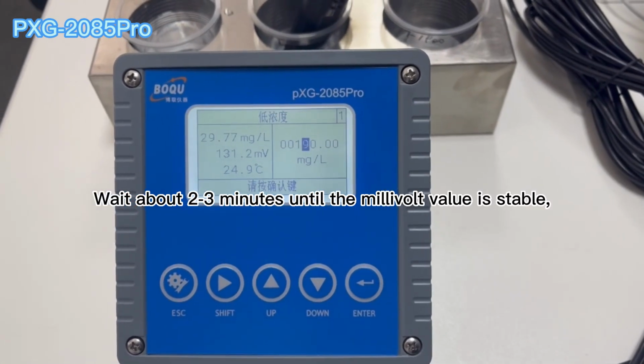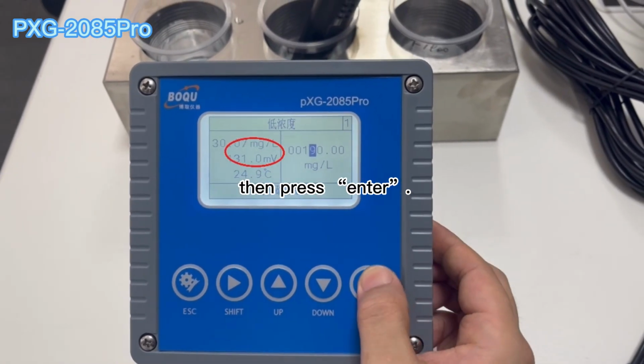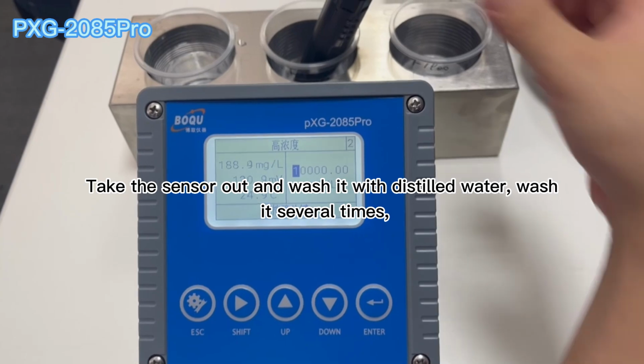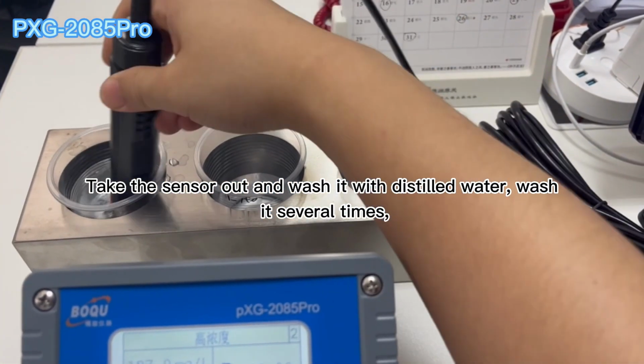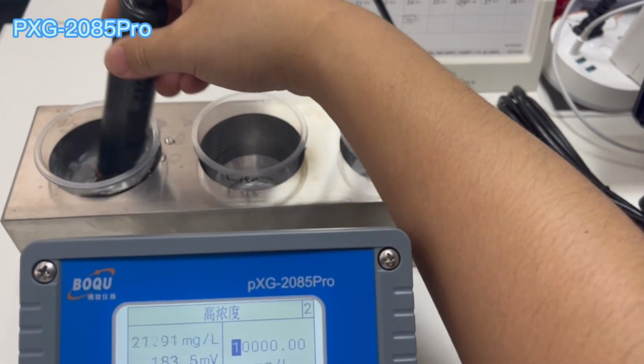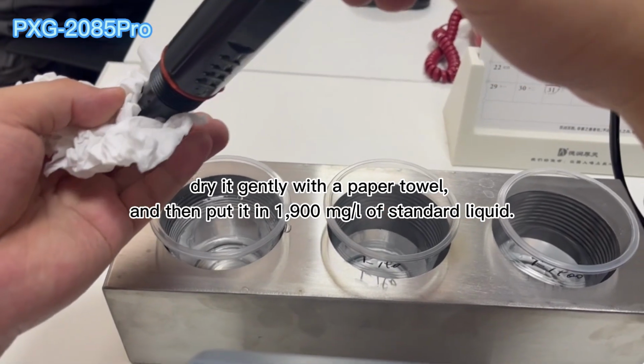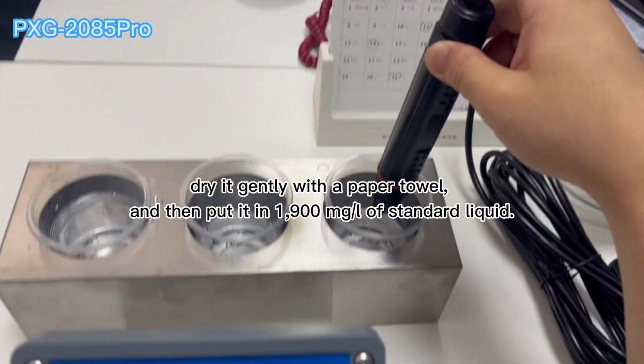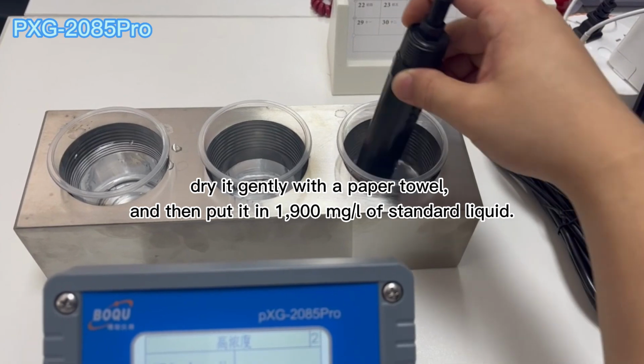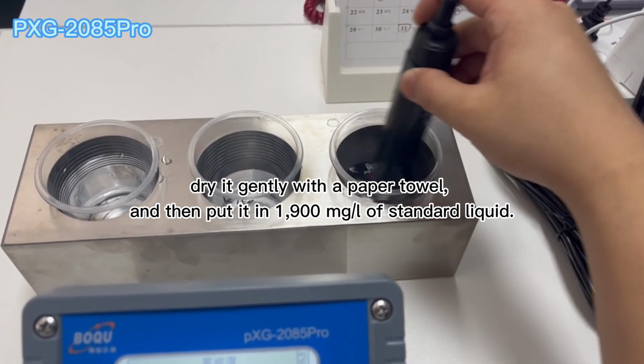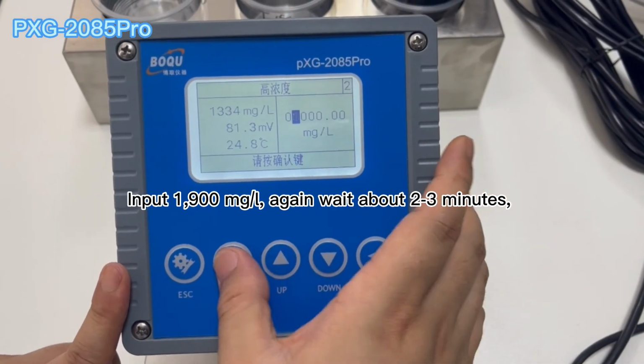Wait about 2 to 3 minutes until the millivolt value is stable. Then press Enter. Take the sensor out and wash it with distilled water. Wash it several times. Dry it gently with a paper towel and then put it in 1900 mg per liter of standard liquid. Input 1900.